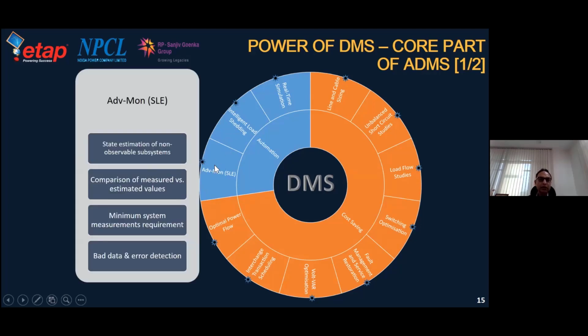This SLE, system load estimation, provides the values at any node or any device which is going to provide analog values such as voltage, current, etc. Through this application, it is particularly helpful when we don't have those devices available in the field, because practically it is not possible to have all devices metered or equipped with such facilities. It also helps to segregate bad data, and prompts if it finds any error in it.